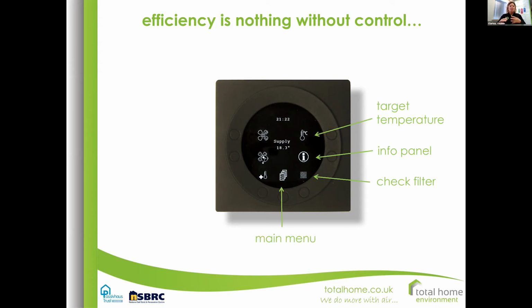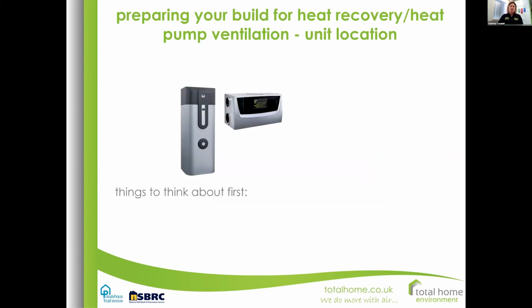Here you've got a main menu where, on commissioning, exact percentage increments will be sorted out for all the airflows and the target temperatures, etc. Here, knowing what your fan speed is, because you don't want the system on at the same level all day. At night it will be on 25%, the day 50% say, perhaps it will boost up to 75 during showers and cooking and stuff like that. And then you should always have the option to manually press on a boost as well. Say if you're going to have a party and you want to have it on for maybe 2 or 3 hours extra, being able to control that and then not have to remember to turn it back down again afterwards is very convenient. If you've got the units that have got extra heating or perhaps an inline duct heater or something like that, that is where you will control that. So you can see this all makes the system much more efficient and much more convenient for you too.